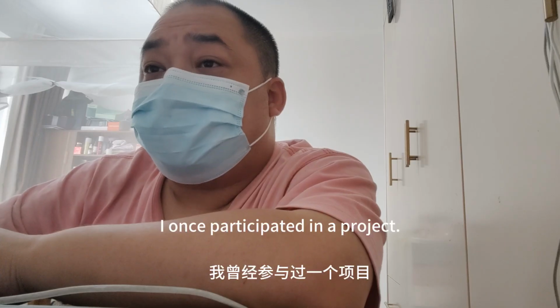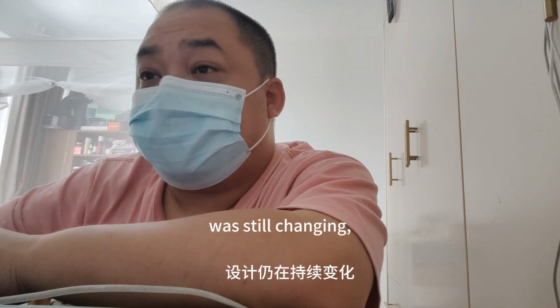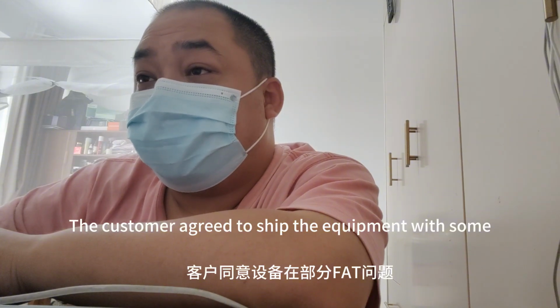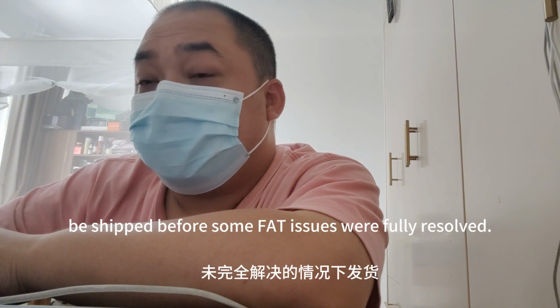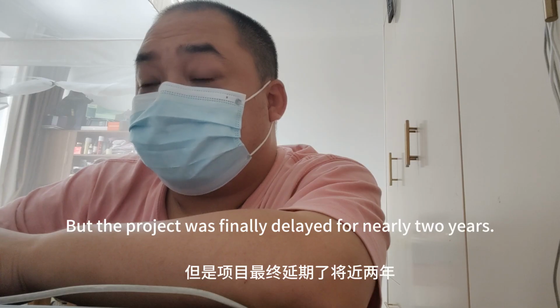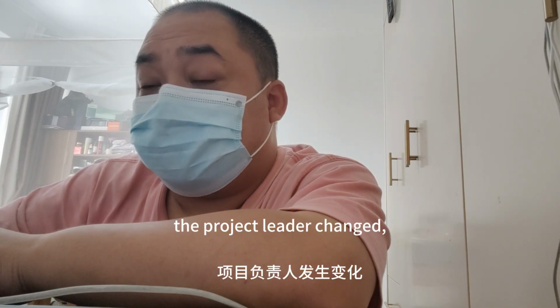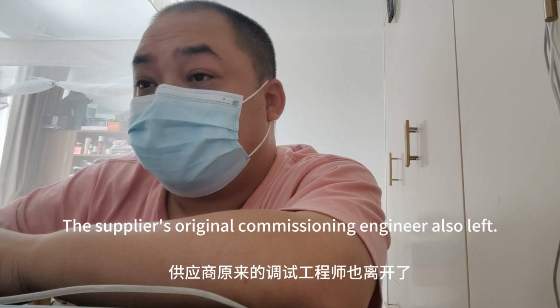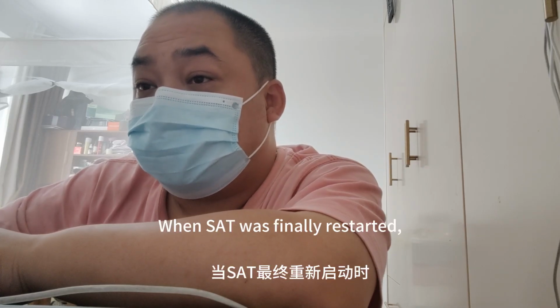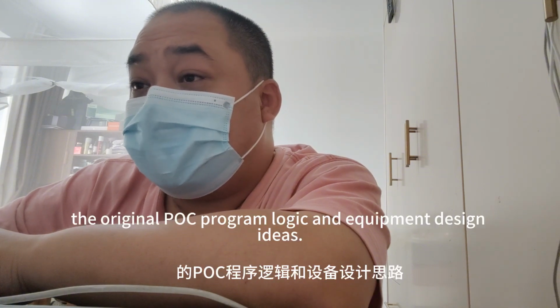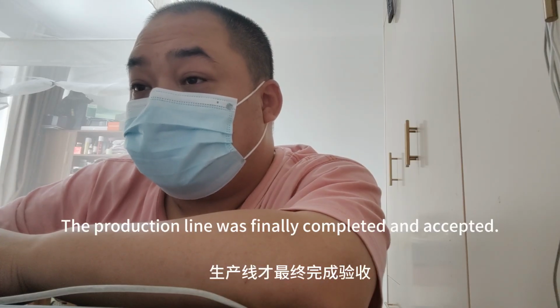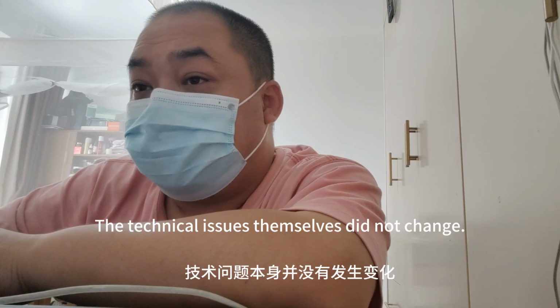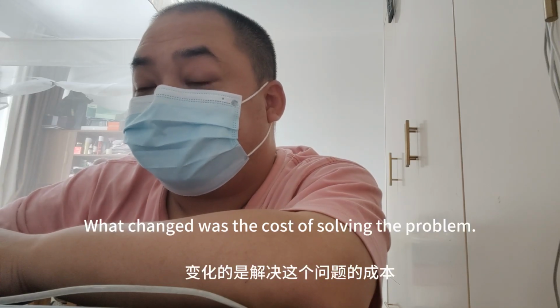Industrial case: I once participated in a project where the customer's own product was still changing. The customer agreed to ship the equipment before some FAT issues were fully resolved. The original plan was to complete SAT soon after installation, but the project was finally delayed for nearly 2 years. During this period, the project leader changed. The purchasing staff left. The supplier's original commissioning engineer also left. When SAT was finally restarted, the new engineer had difficulty fully understanding the original PLC program logic and equipment design ideas. It required several months of extra work. The production line was finally completed. The technical issues themselves did not change. What changed was the cost of solving the problem.